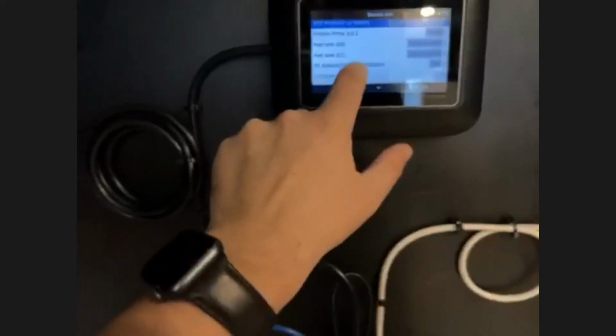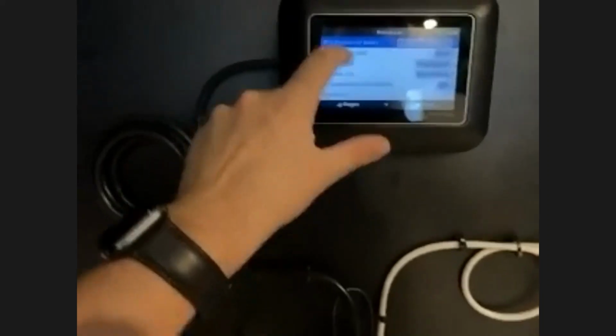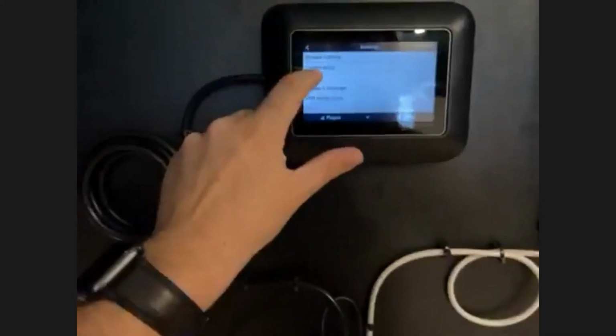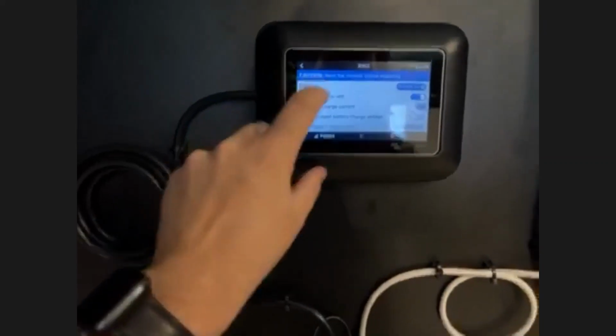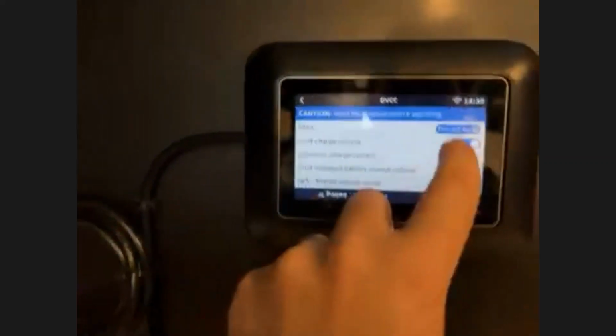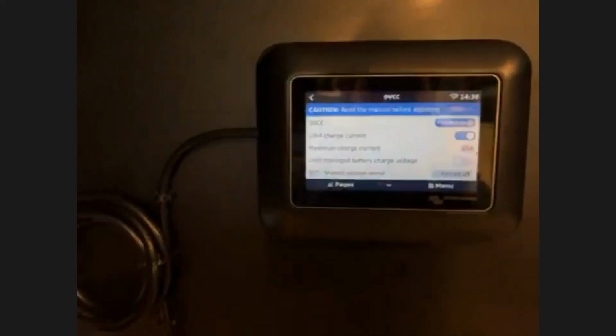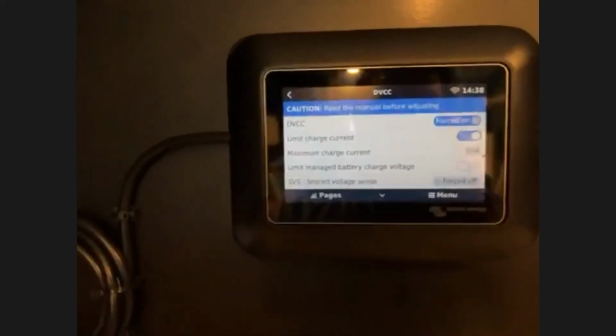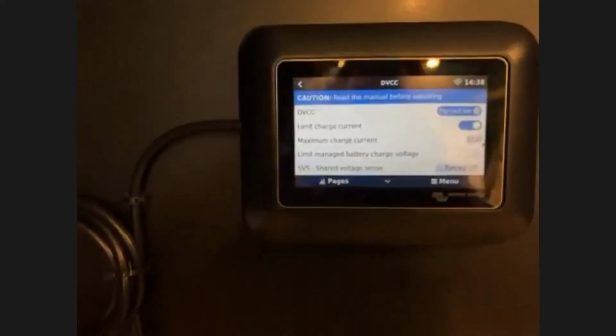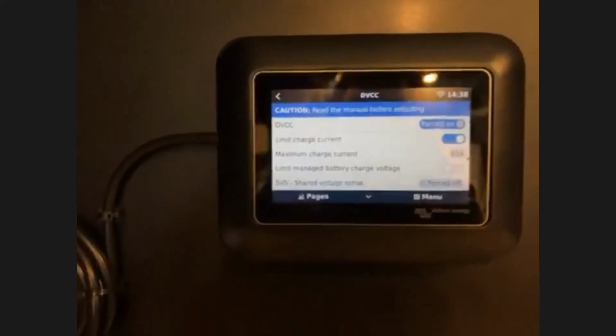The Cerbo GX detects the BYD battery. If we head in now, this is managed through a system called DVCC. We head into the DVCC menu, and you can see DVCC here is forced on. The system detected that it's a BYD battery, and as a consequence, DVCC must be enabled, and that happens automatically when the system's connected through the BMS CAN port.